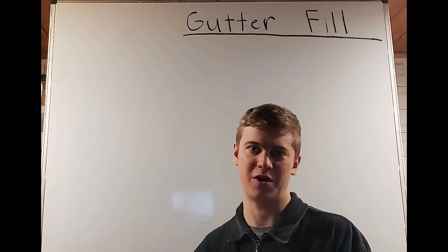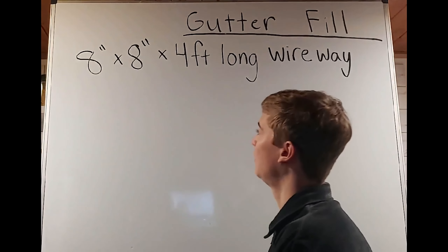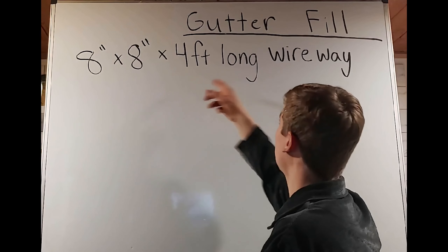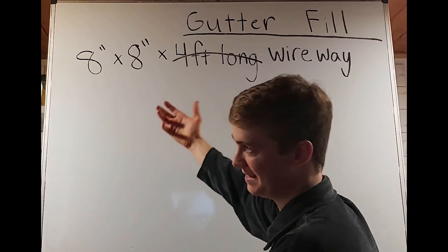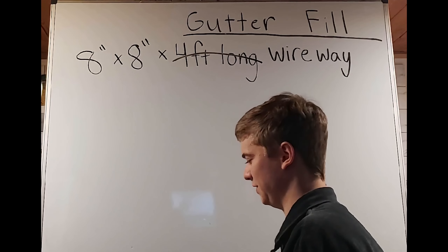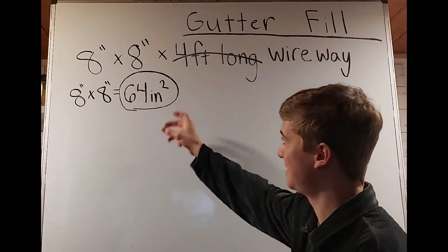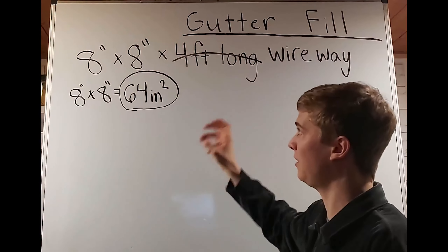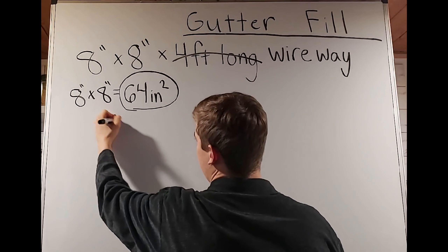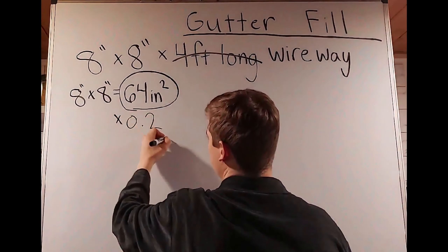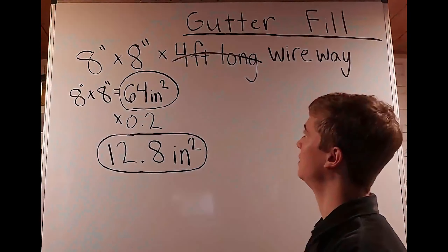For the next question, I'll break it into two parts. We have an 8-inch by 8-inch by 4-foot-long wireway. We disregard the fact that it's 4 feet long. We know it's 8 inches by 8 inches, so 8 times 8 gives us 64 square inches. We're not done — 64 square inches is the total area, but we only want 20% of the total area. So we do 64 square inches times 0.2, which gives us 12.8 square inches. That's how much we can fill this wireway.